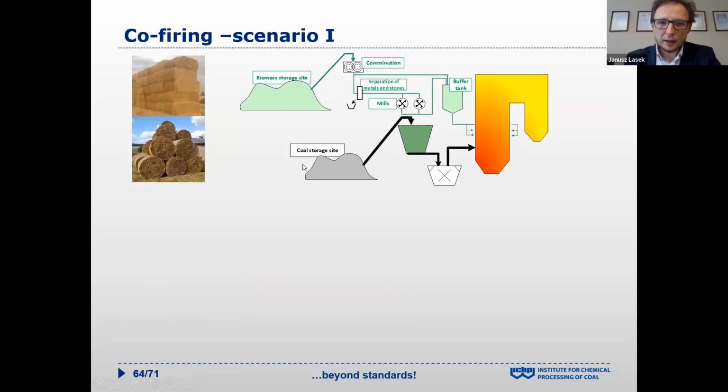Let me say something more about it. Janusz, just one clarification question. So for pulverized boilers, milling is necessary, yes? Necessary, for sure. The particles must be lower than 1 millimeter, approximately between 20 and 200 micrometers. This is the point. We have to use the mills, in fact.